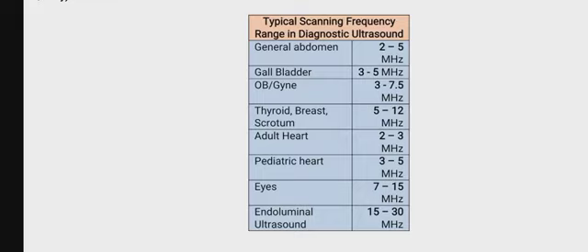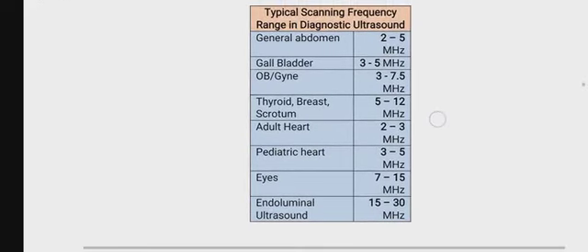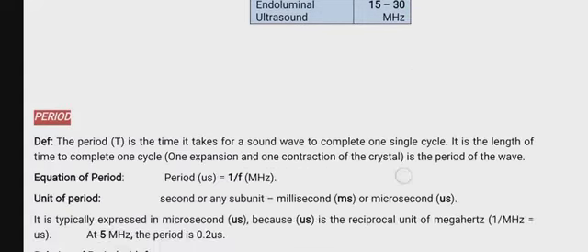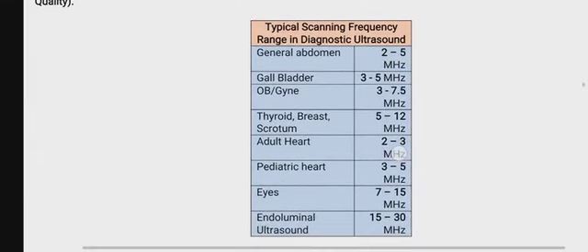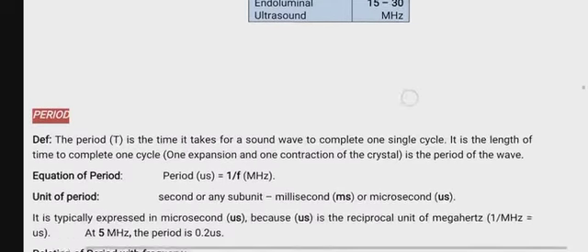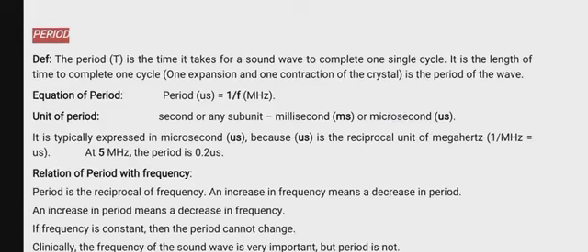Adult heart, if you are doing a cardiac examination, 2 to 3 megahertz. Pediatric heart, you can use 3 to 5 megahertz. Of course, the chest of an adult is more bulky than that of children, so you understand the trade-off between the depth and quality here. For eye, ocular scan, 7 to 15 megahertz, and endoluminal ultrasound is 15 to 30 megahertz. That's for making a discrete choice for your ultrasound transducer with respect to your area of interest.